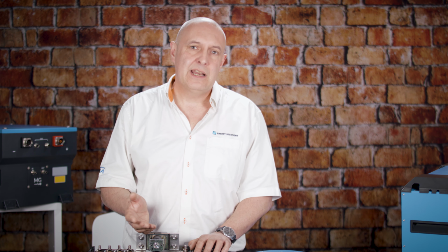We can provide higher levels of power for a shorter duration, and at the kind of upper limit of that is a 1.5C discharge rating that's quoted as around about a 10-second rating. So in our example, we'd be able to pull 36 kilowatts from this battery bank for a very short period of time, but that's a kind of a curve that falls away down to our continuous rating.